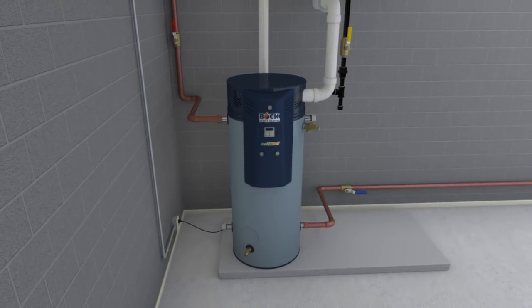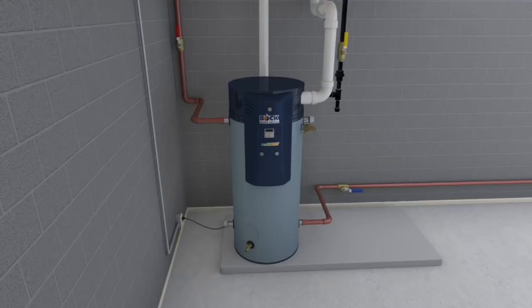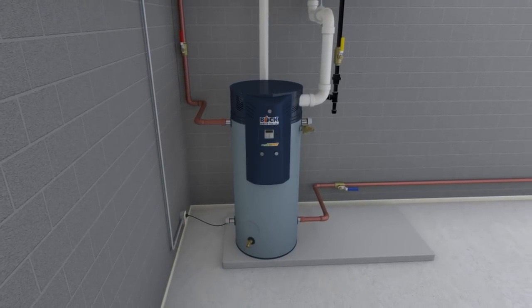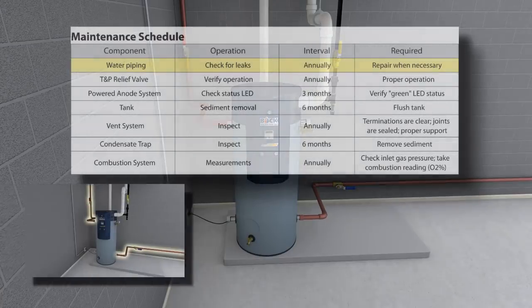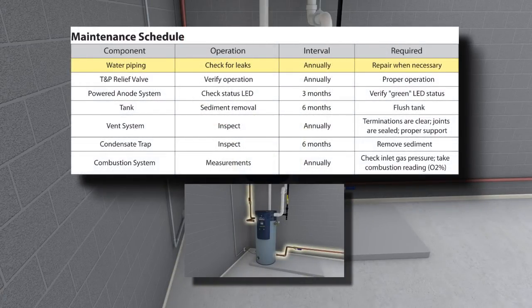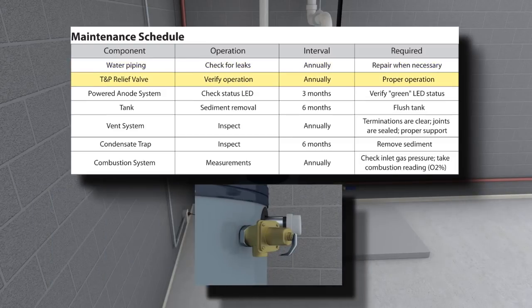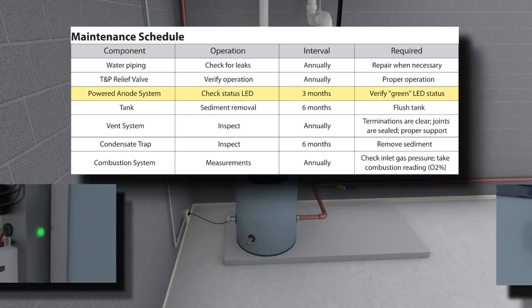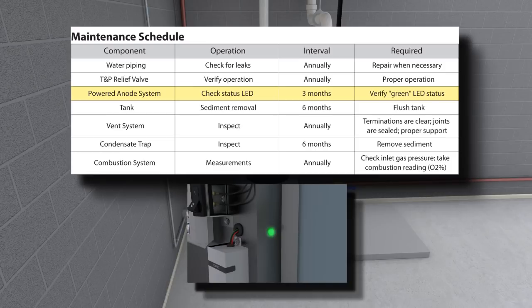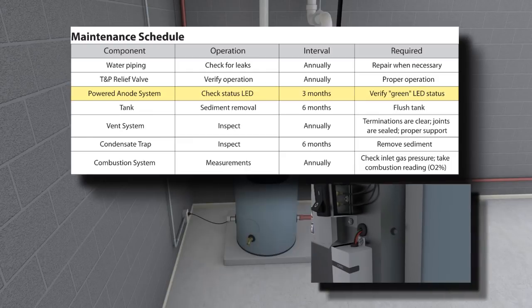Regular maintenance must be performed at the proper time interval. A chart in the manual provides a list of when certain tasks should be performed. Water piping. All water piping, valves, unions, and joints should be checked for leaks annually. The T&P valve. Every year the T&P valve function should be checked. The cathodic protection system. The module and status LED are mounted on the control panel under the cover. The status LED will be green if the system is functioning properly. The LED will flash red if there is a system error.